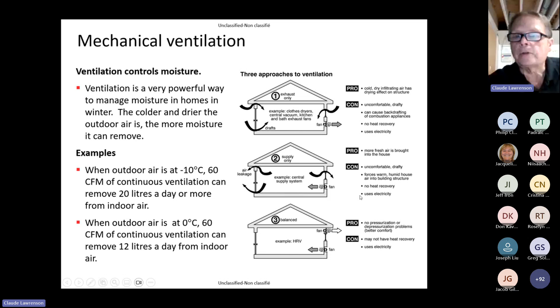If we have a balanced system, which is the ideal system, which the code talks about, the example is the HRV, heat recovery ventilation. There's no pressurization or depressurization problems. In other words, balance. It may not have heat recovery, and it certainly uses electricity. So again, there are 3 approaches to mechanical ventilation.